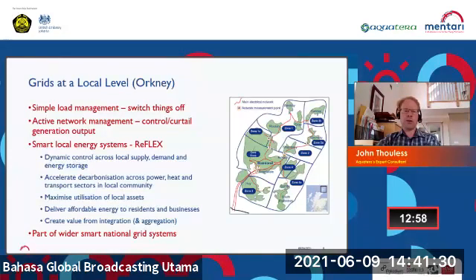The way we could control that at one time was a crude, binary approach of switching off wind generators. So around 10 years ago, the system moved to active network management, which basically controlled the output of those wind turbines. We'd bring down output in a controlled way to match demand, driven by pinch points on the network—if those points saw excess flow and the grid was stressed, we could pull back generation on the other side so the network wasn't overloaded.